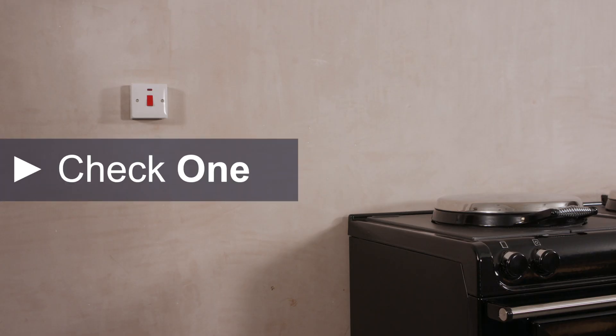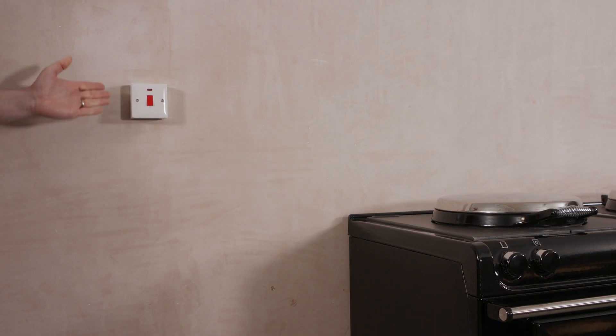Check number 1. You will need an accessible isolation switch that is within 2 meters of the cooker, but not above or behind it, and in the same room. The Aga will need a dedicated 32 amp electrical supply using a minimum 6mm feed direct from the consumer unit.